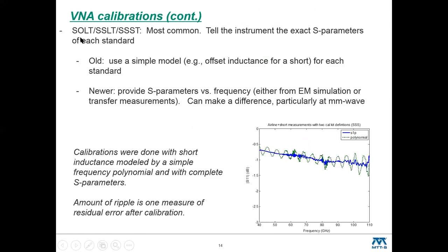Open short load is probably the calibration method people are most familiar with, and it has some relatives based on offset shorts and a load, or just offset shorts. The premise of these techniques is you tell the instrument exactly what the S parameters are of each standard, and the instrument will do what it has to in order to reproduce those values it's told.